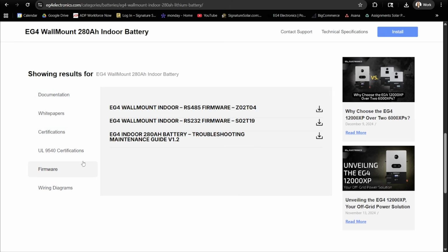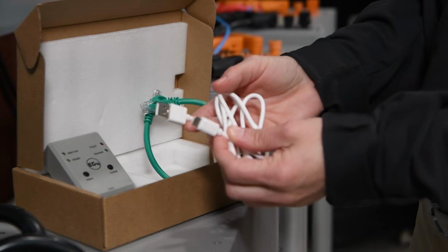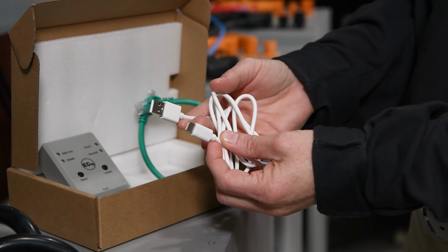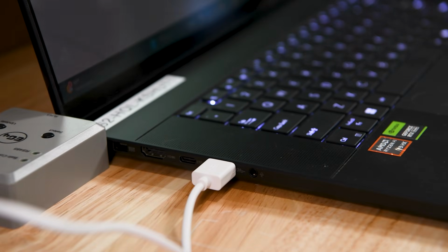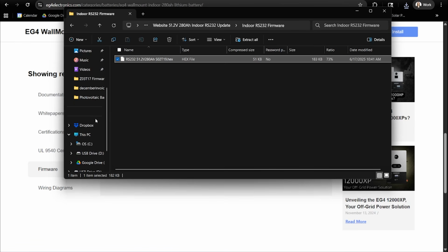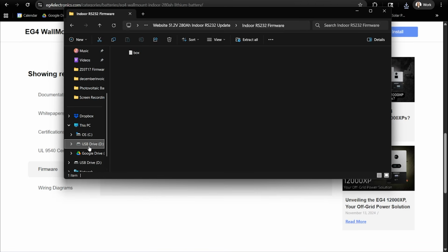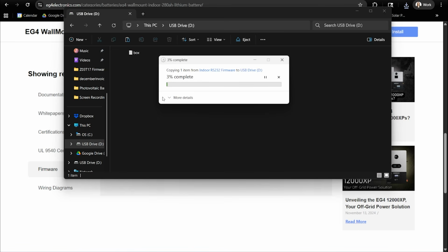If both RS485 and RS232 files are provided for that model, download both. Using the USB-A to USB-C cable that comes in the box, plug the EG4 battery firmware adapter into your computer. When the adapter appears as a removable drive, copy both firmware files into the adapter's folder. Safely eject the adapter once the files are transferred. Only firmware files for one battery type should be on the adapter.